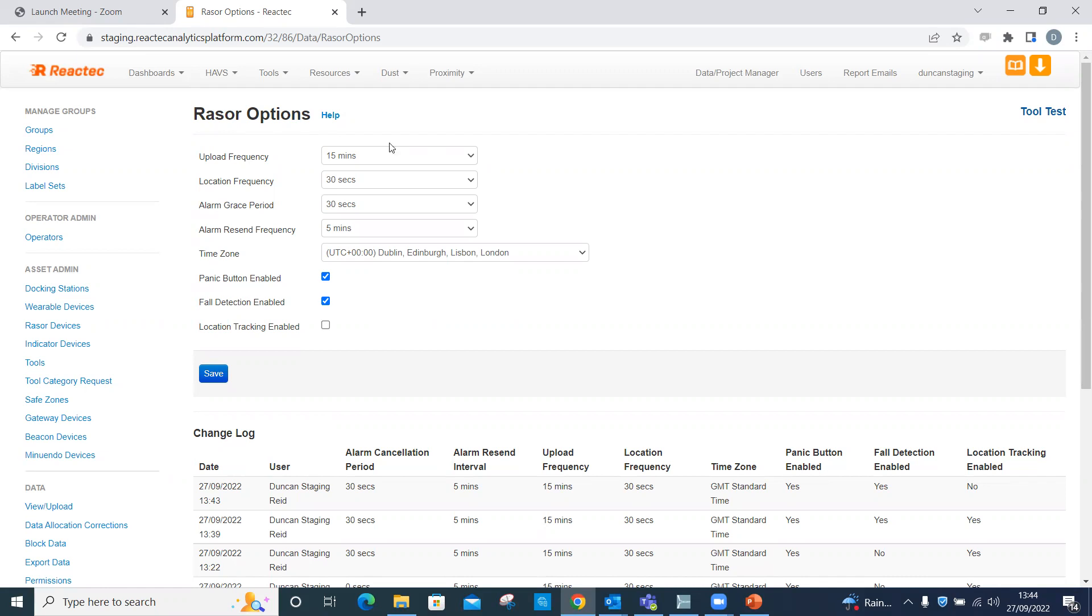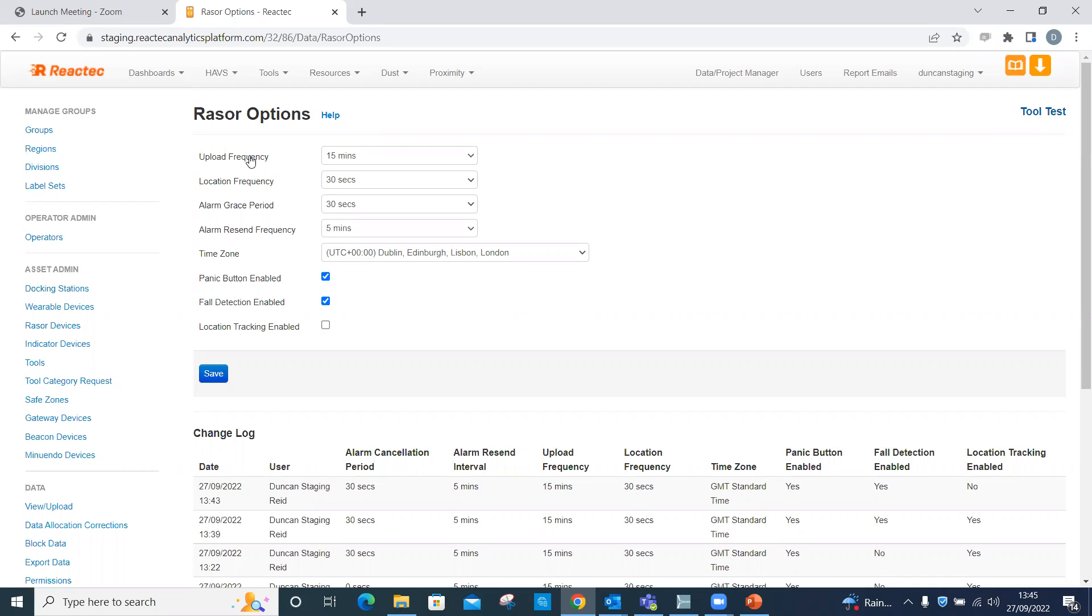Upload frequency. This defines how often the Rasor sends data to the analytics. The frequency of data uploads from the Rasor to the analytics default is 15 minutes. The exception to this is in the case of an alarm. In this case, the data would be sent immediately. The minimum frequency is set to one minute as frequent data transmissions impacts the battery life of the Rasor.